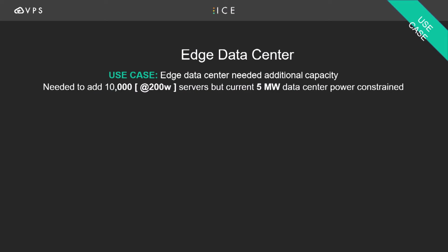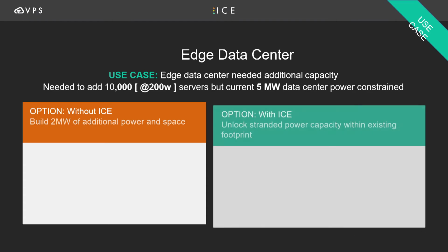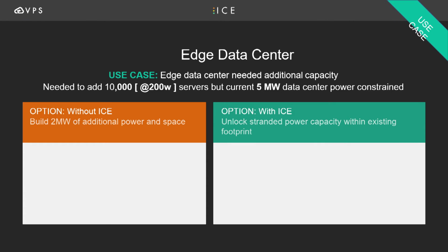This edge data center has 5 megawatts and wanted to add another 10,000 servers, reckoning about 200 watts per server, which is about 2 megawatts. So they're going to have to add 2 megawatts, meaning they'd have to build a new data center for 2 megawatts. It's going to take a few years, and they'd have to provision about $20 million in CapEx and about $1.4 million or so in OpEx every year.